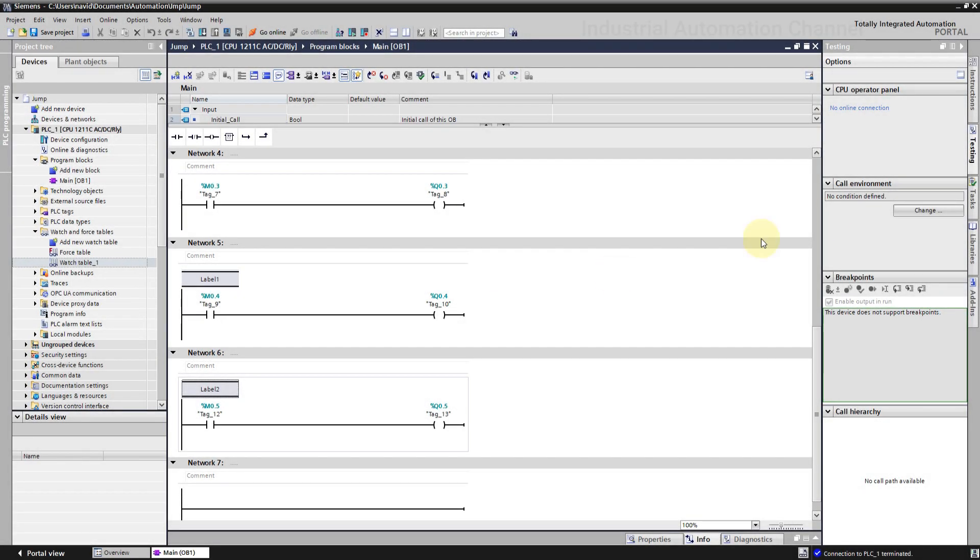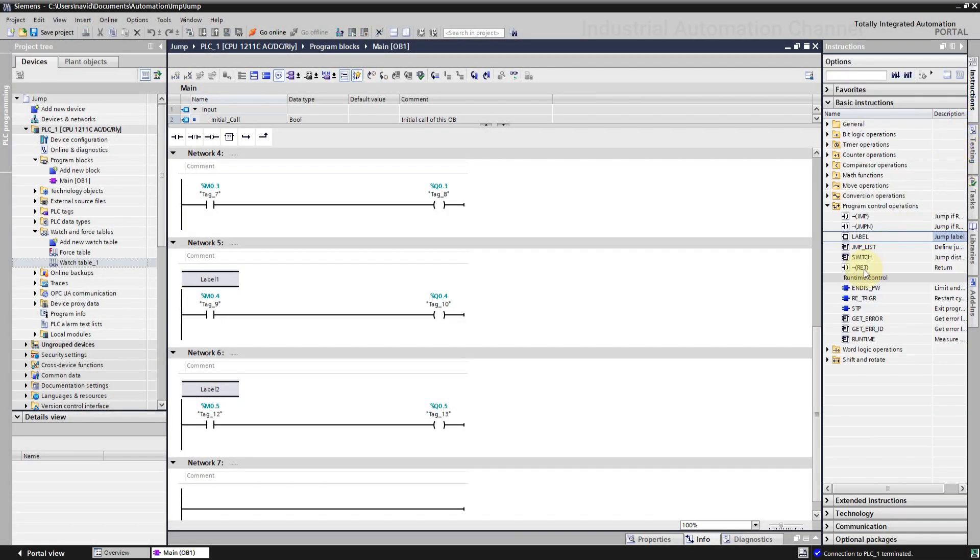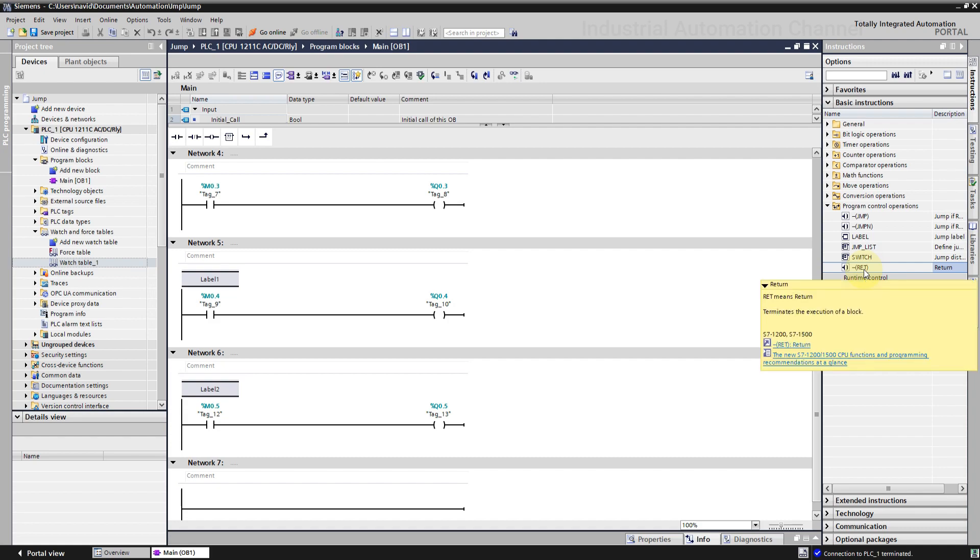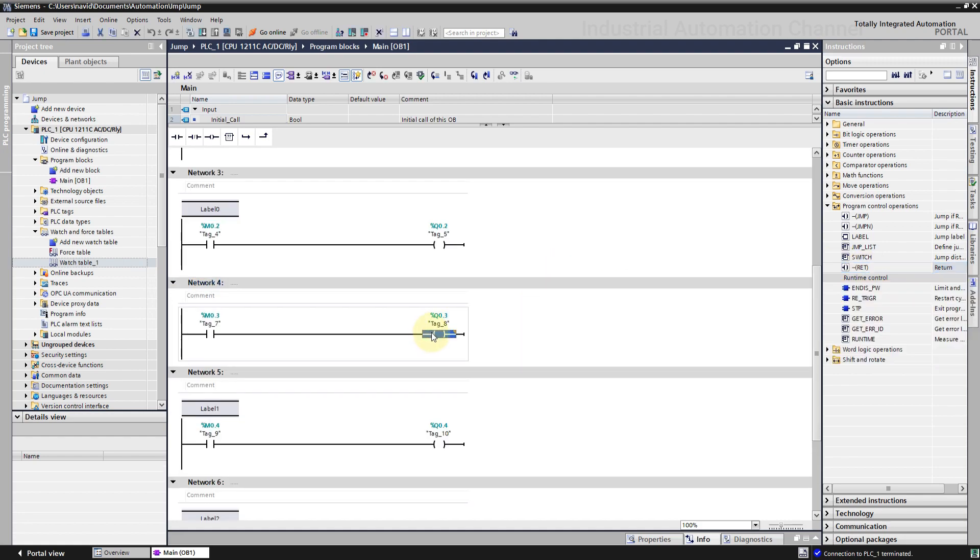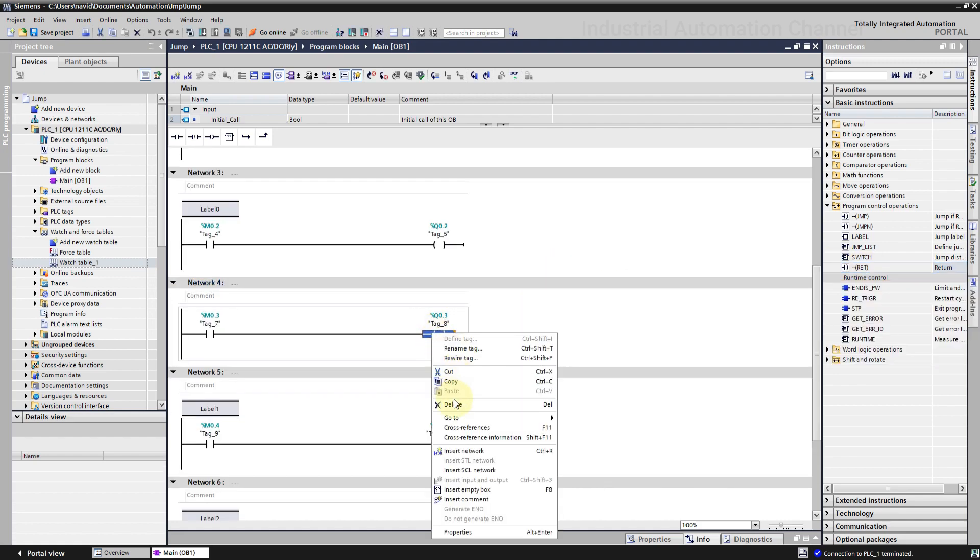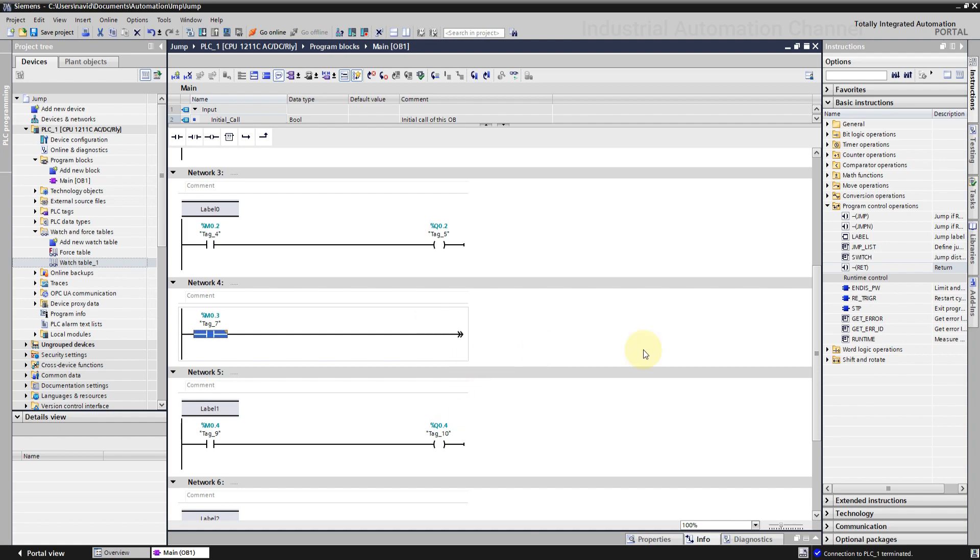The last instruction is return. We can use the return instruction to stop the execution of a program block. It means when return is activated, the program will be scanned from the top to the bottom. But when it reaches the network with return, it will stop scanning the program. The networks under this return will not be executed. If we use return in a function or function block, CPU will exit from FC or FB and will return to its previous block.